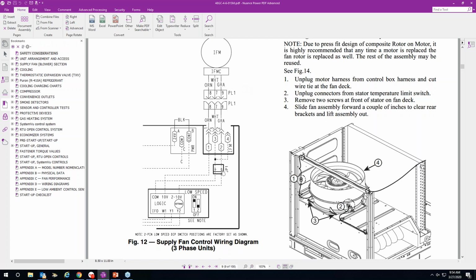There is a jumper right here, a jumper plug. Make sure that's intact. Make sure there's nothing going on there. Again, make sure all the dip switches, if you've got 2 for 3-phase or the 7 total for single phase, are making contact, and I would exercise them just to eliminate that, because I've seen that before on boards where the switch is in the position it's supposed to be according to the setup, but by exercising the switch, all of a sudden my signal comes back. So it could be something like that.